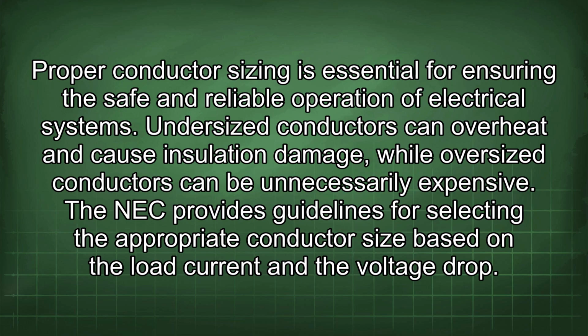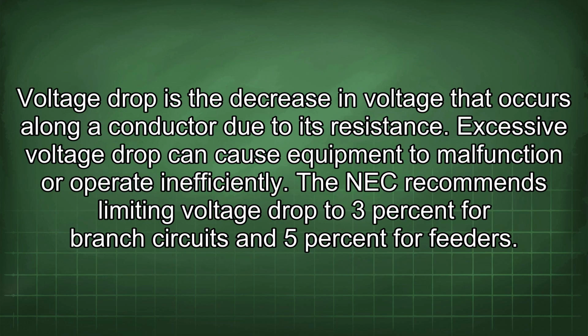Undersized conductors can overheat and cause insulation damage, while oversized conductors can be unnecessarily expensive. The NEC provides guidelines for selecting the appropriate conductor size based on the load current and the voltage drop. Voltage drop is the decrease in voltage that occurs along a conductor due to its resistance. Excessive voltage drop can cause equipment to malfunction or operate inefficiently. The NEC recommends limiting voltage drop to 3% for branch circuits and 5% for feeders.